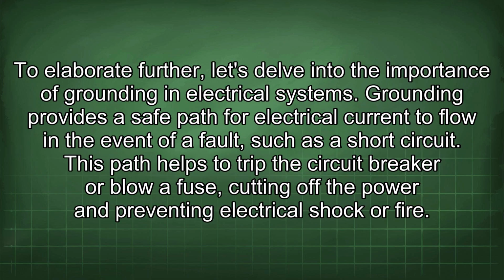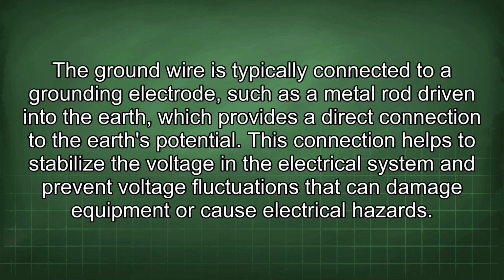To elaborate further, let's delve into the importance of grounding in electrical systems. Grounding provides a safe path for electrical current to flow in the event of a fault, such as a short circuit. This path helps to trip the circuit breaker or blow a fuse, cutting off the power and preventing electrical shock or fire. The ground wire is typically connected to a grounding electrode, such as a metal rod driven into the earth, which provides a direct connection to the earth's potential.